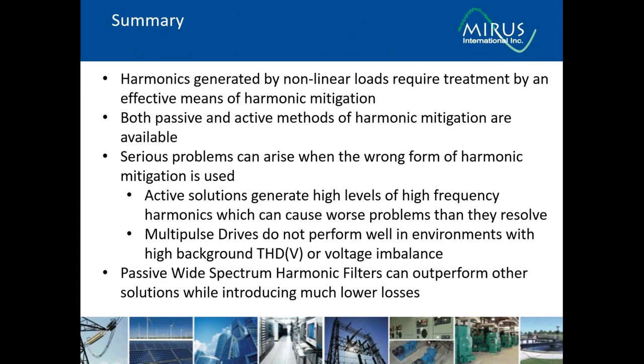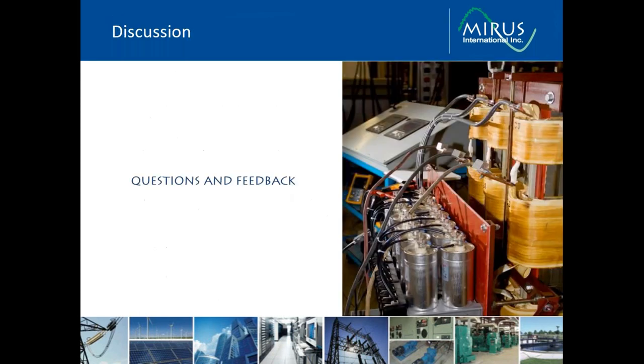So in summary, harmonics generated by nonlinear loads require treatment by effective means of harmonic mitigation. Both passive and active methods are available. Serious problems can arise when the wrong form of harmonic mitigation is used. Active solutions generate high-frequency harmonics, which can often cause worse problems than they are trying to resolve. Multipulse solutions do not perform well in environments with high background voltage distortion or voltage imbalance, and both introduce higher losses than you would get with a passive wide-spectrum harmonic filter, which therefore performs better than those other solutions. So that wraps up the seminar.